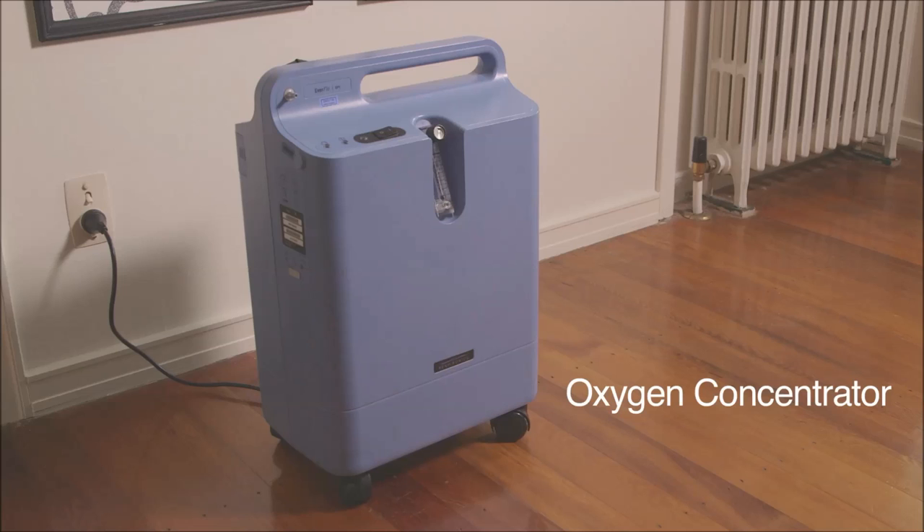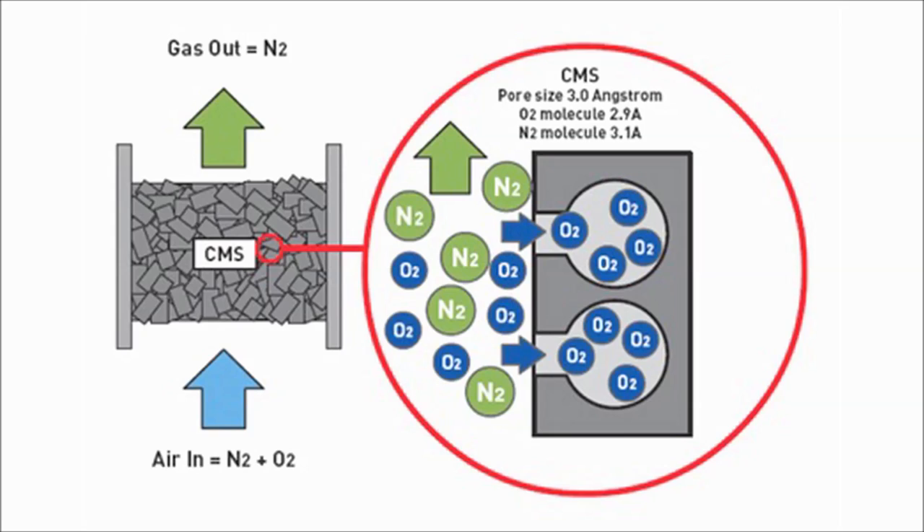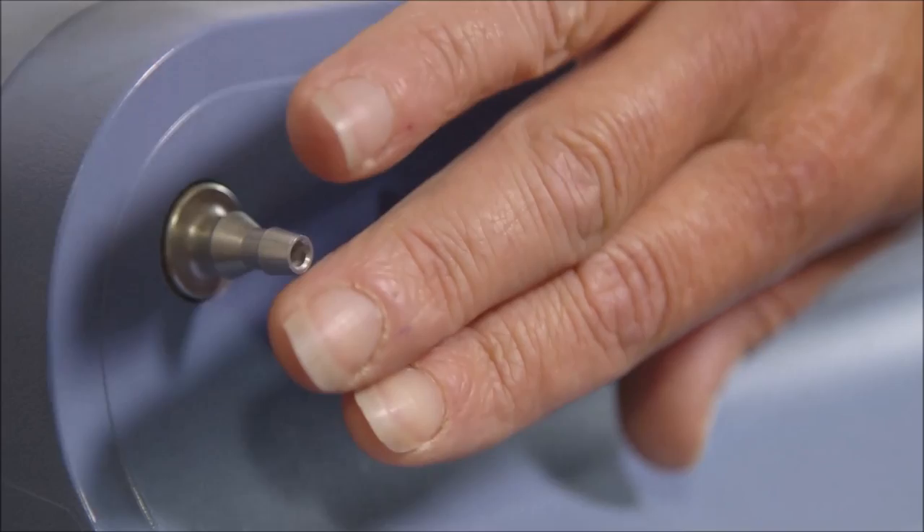This is Section 2, on your oxygen concentrator. I am going to show you how to use your oxygen concentrator safely. We predominantly use the Respironics EverFlo concentrators. This machine works by taking in air from the environment and separating the oxygen from it using a molecular sieve and pressure swing adsorption process, then pumping the oxygen out through the oxygen outlet port.